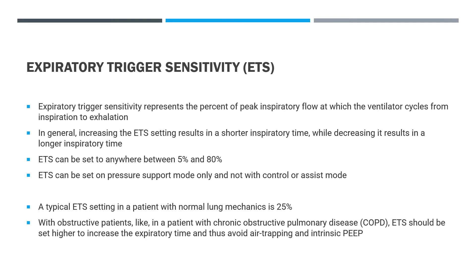We discussed inspiratory trigger. Now we will discuss expiratory trigger sensitivity. Expiratory trigger sensitivity represents the percent of peak inspiratory flow at which the ventilator cycles from inspiration to expiration. Expiratory trigger sensitivity can be set only on pressure support mode and not on assist control mode. An increase in expiratory trigger sensitivity, for example from 25% to 40%, results in a shorter inspiratory time.